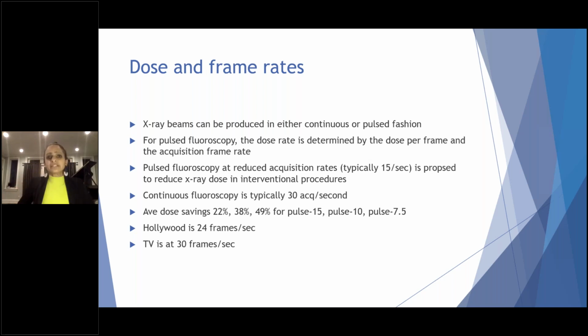So what is continuous versus pulsed? Well, continuous fluoroscopy is about 30 frames per second, whereas pulsed can range. It can range around 7.5. According to my X-ray techs, the pulse on ours is set to be 8 frames per second. It can be 8, 10, 15, something like that. What I've read is that it's typically around 15 frames per second.